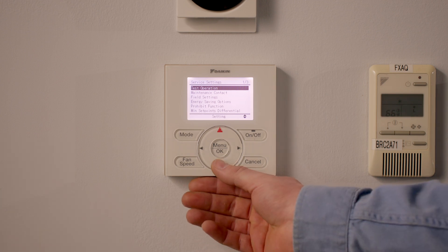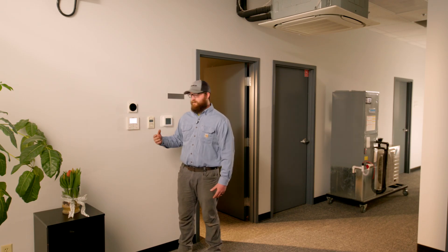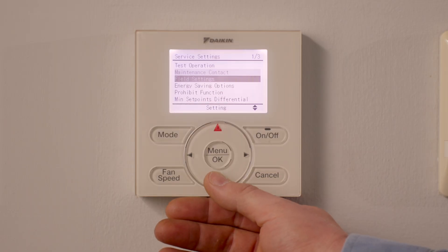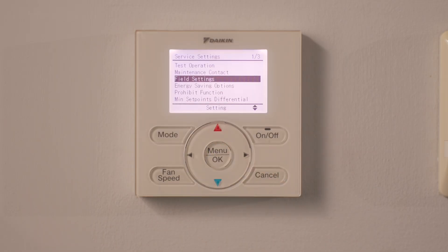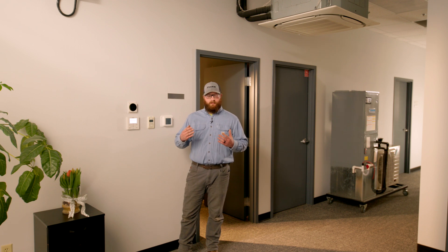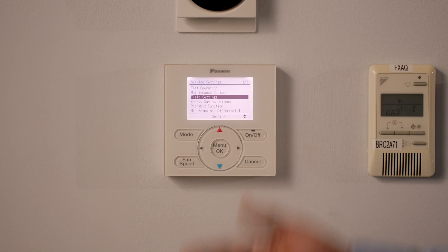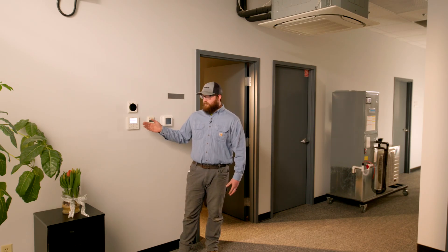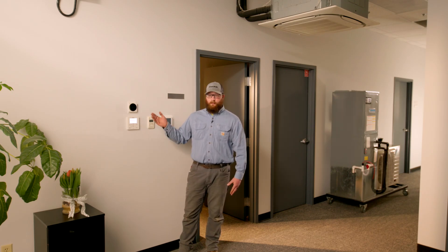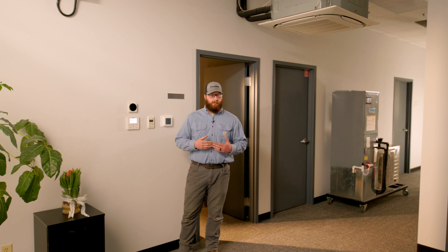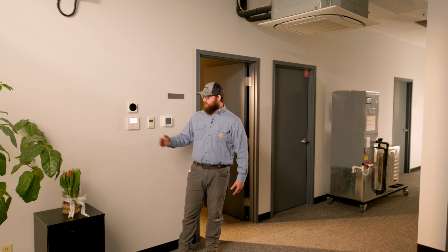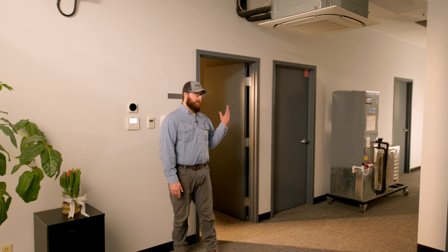You'll see a plethora of different settings. Primarily what we live in in the commission and startup world is the field settings, which is where we're going to basically tell the unit what thermistor to operate to, whether or not we want to control the fan on thermo on or off — meaning when it's done satisfying the space temperature, is it going to shut that fan off or leave it on? We can also tell the unit what thermistor do we want to control the temperature to — the thermostat thermistor or the return air thermistor?